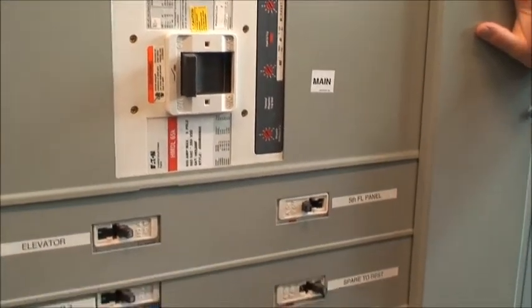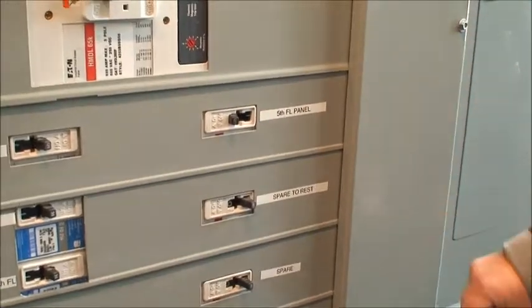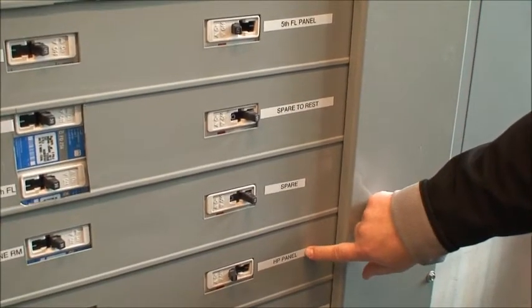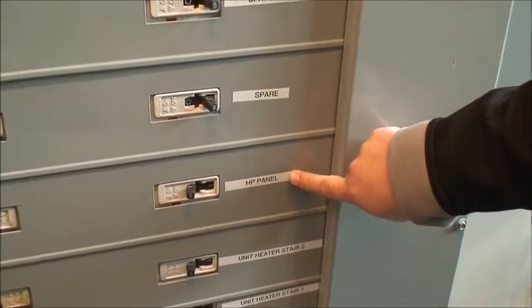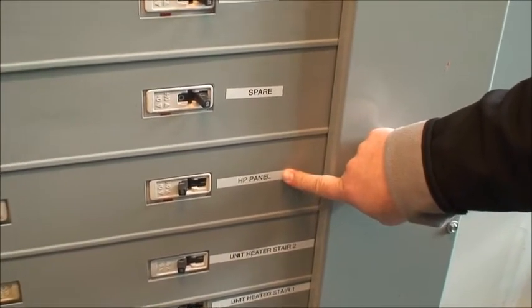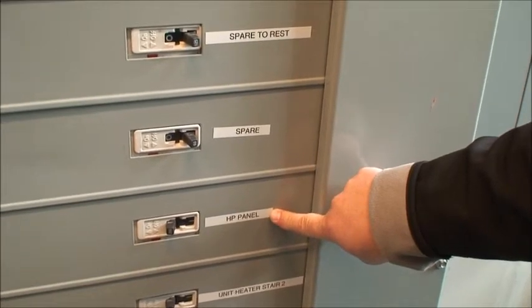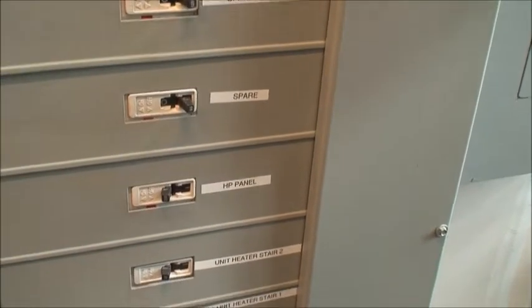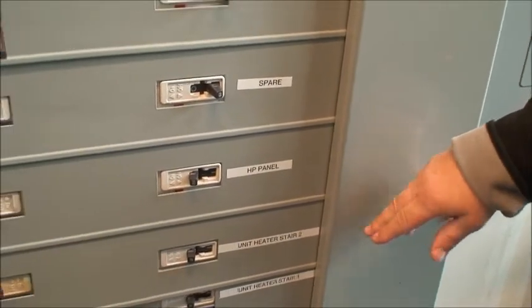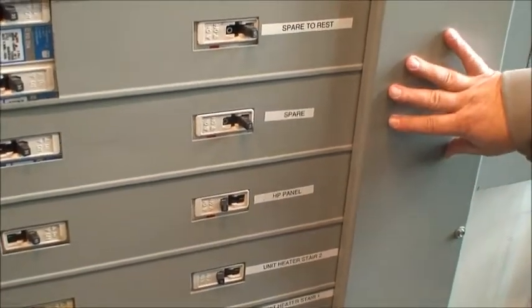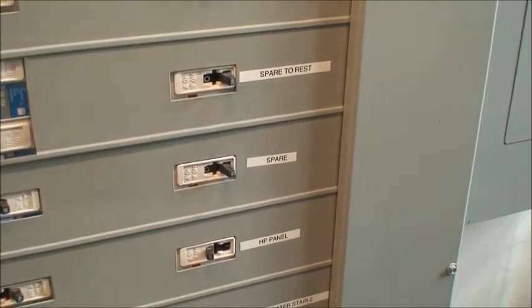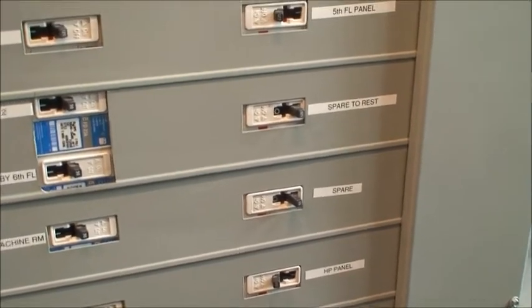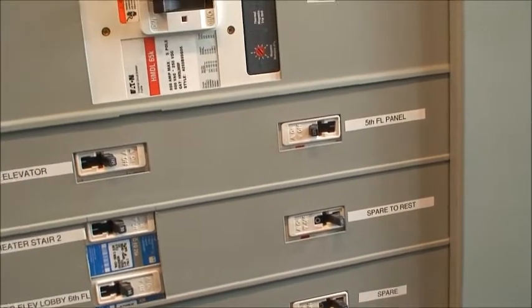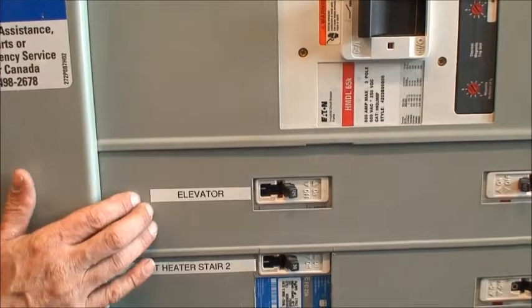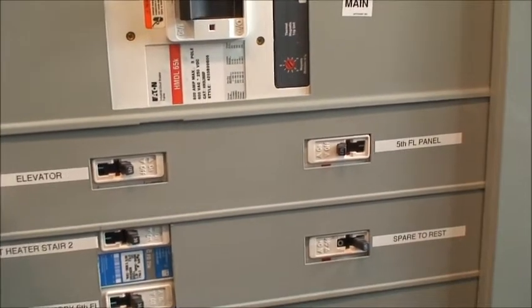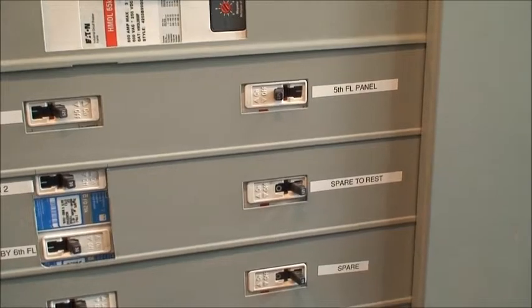We have 2 spares? Yes, you do. There's also this HP panel, which is up on the 5th floor, which was a change to the original documents. We found that to be more practical because there's more to feed up there off of that panel, rather than running several sub feeders to here. We ran one, we upgraded that, and then from that panel there's more. There's roof units, there's elevators, although the elevator I believe is here. Yeah, that's right here. The elevator's here, but everything else other than the elevator that's up on the roof comes out of that panel.